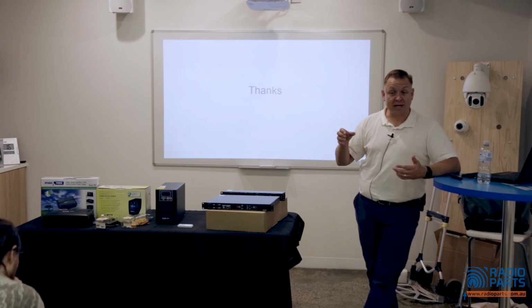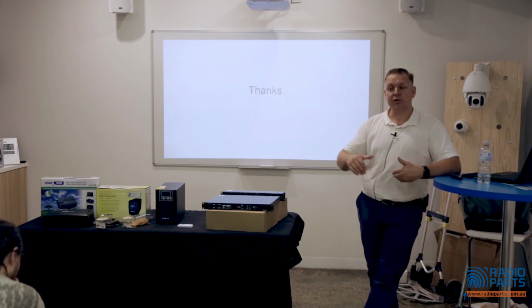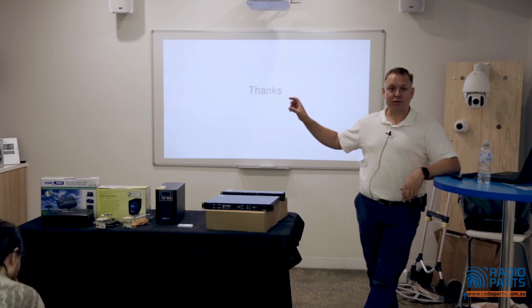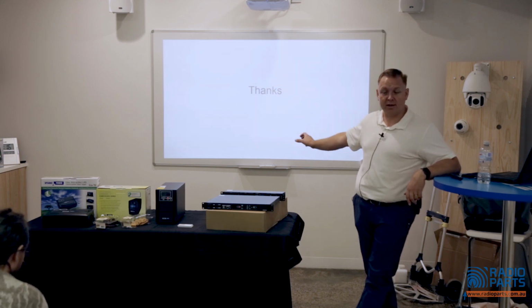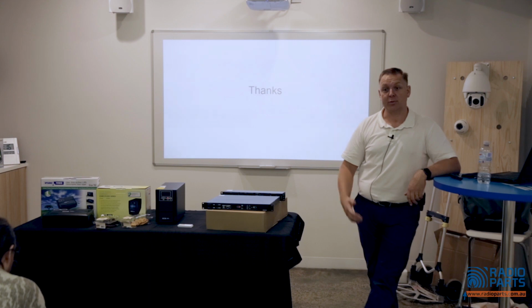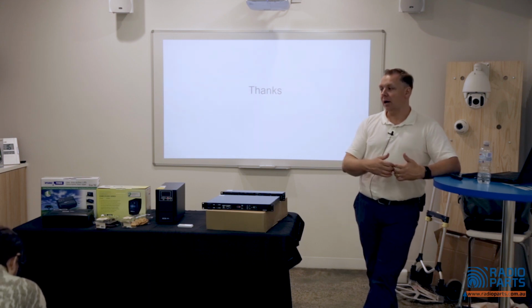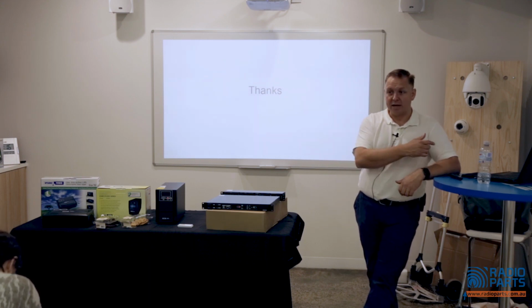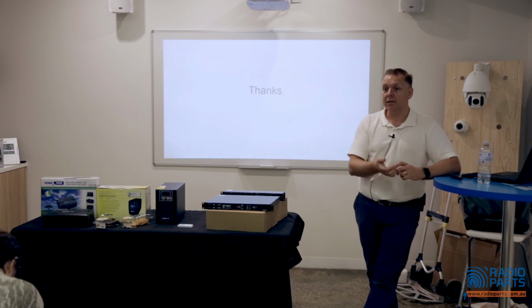On really critical applications, it can actually be tuned to control exactly which harmonics you're looking at if there's other issues. So you can actually use a UPS to filter harmonic distortion from a bad load back to the mains as well. So as we start talking about power factor and things like that, we talk about billing.